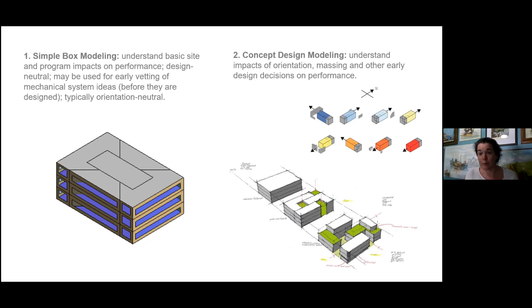Load reduction modeling is understanding the impacts of things like window-to-wall ratio, solar shading, maybe floor-to-floor height and duct sizing on a high air change rate building—understanding peak loads. Those affect your system sizing: how many chillers, what size chillers, how many boilers. HVAC capacity is based on peak loads, not annual energy use, yet we do all our modeling based on annual energy use or cost. But you want to know what the peak is, and can I reduce it, because that's where we get construction cost savings.